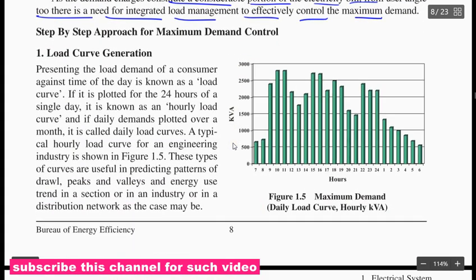Step-by-step approach for maximum demand control. Presenting the load demand of a consumer against the time of day is known as a load curve. If plotted for 24 hours of a single day, it is known as an hourly load curve. If the daily demand is plotted over the month, it is called a daily load curve. A typical hourly load curve for an engineering industry is shown in the curve. These types of curves are useful in predicting patterns of demand, peaks and valleys, and energy use trends in the section of industry or in the distribution network, as the case may be.